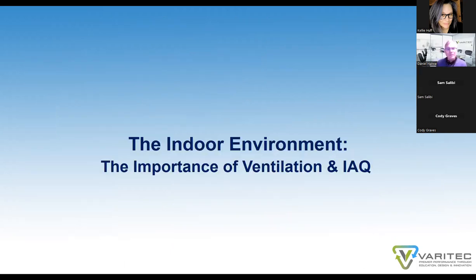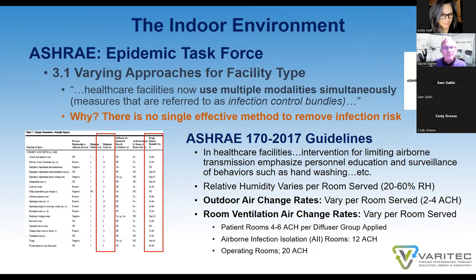So the indoor environment. What is the importance of ventilation and the importance of indoor air quality? Per the ASHRAE Epidemic Task Force, it was very apparent, and ASHRAE has argued for a long time, there is no one single method to reduce the risk of infection in a building and to provide better indoor air quality. Consequently, the Epidemic Task Force leaned on the modality they set up for hospitals, and that is to use a multiple modality approach. In other words, use two or three various solutions to help create a healthier indoor environment. ASHRAE Standard 170, which writes the healthcare standards, actually defines that in a couple of ways: by increasing building humidity, increasing air change rates in rooms, increased ventilation rates, et cetera.